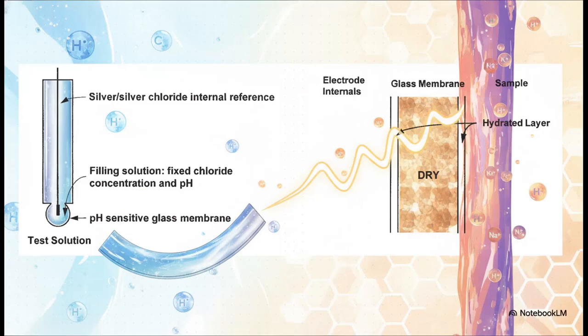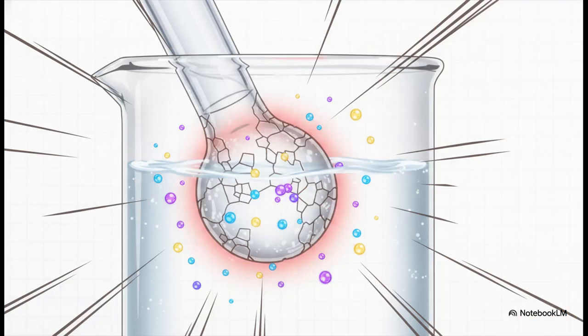Deep inside the reference internal, you'll find a silver/silver chloride setup. It sits in a filling solution with a fixed chloride concentration, which locks its potential perfectly in place. But the real magic happens over in the critical hydrated glass layer. This is the absolute heart of the measurement. The pH glass membrane actually absorbs water, creating this microscopic gel layer that's only about 50 nanometers thick. It's the ion exchange between the alkali metals in this wet layer and the hydrogen ions in your sample that physically generates the voltage. And that leads us to the absolute golden rule of pH measurement.